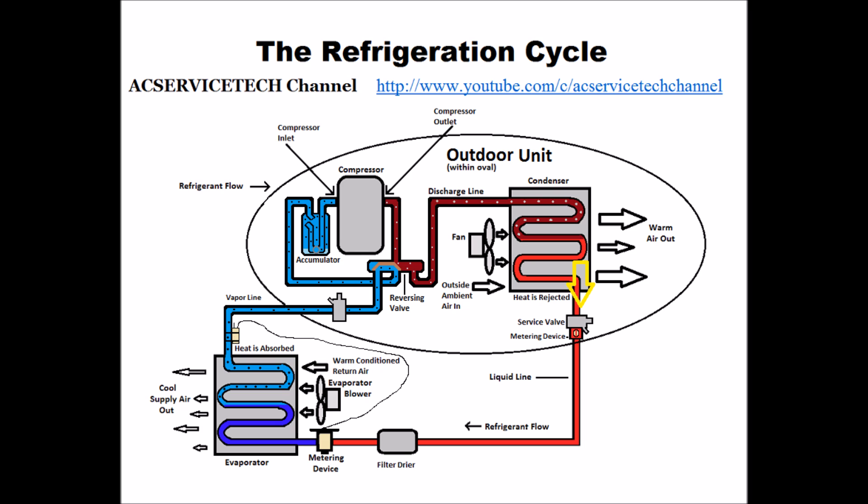It then goes into the service valve and through the non-active metering device. Regardless of where that metering device is located on a heat pump, the refrigerant is going to flow around it and through it — so it's not active at this point, it's kind of like a bypass. It's still a high pressure, high temperature liquid refrigerant even though it's rejected heat in the outdoor coil.